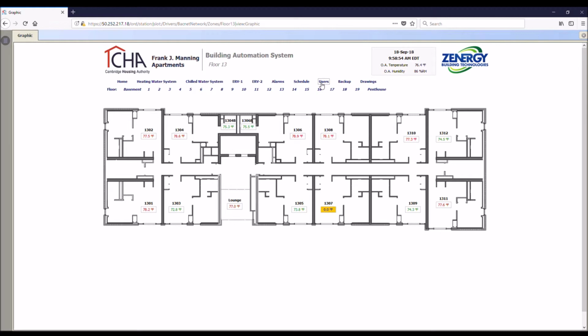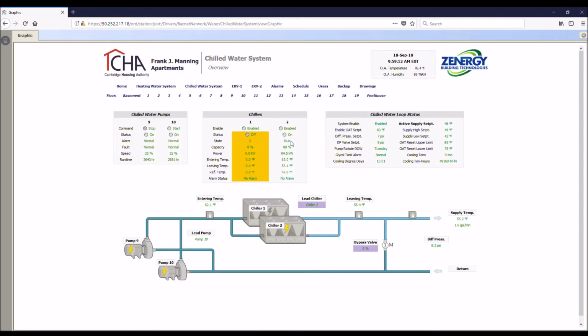That's pretty much the only background colors you'll see. If the system is trying to load a point, you'll see a gray background. I don't know if we go to a page, which we'll run into that. If we go to the chilled water system. But if it's gray, basically the system is trying to go and ask for that point value, and it's just waiting to get it. That's called stale. So it just means we haven't read that point in a while, so we can't verify the validity of the value. But we're trying to re-pull the point. And if something stays too stale for too long, then it'll most likely go into fault because we had a communication error. Stale doesn't necessarily mean an error; it just means that we haven't talked with that controller in a while.